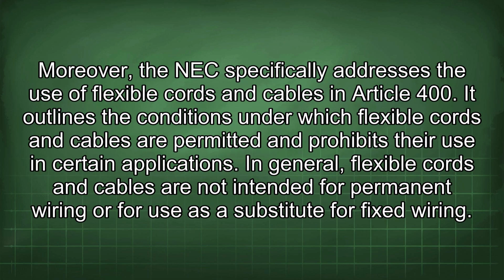Moreover, the NEC specifically addresses the use of flexible cords and cables in Article 400. It outlines the conditions under which they are permitted and prohibits their use in certain applications. In general, flexible cords and cables are not intended for permanent wiring or as a substitute for fixed wiring.